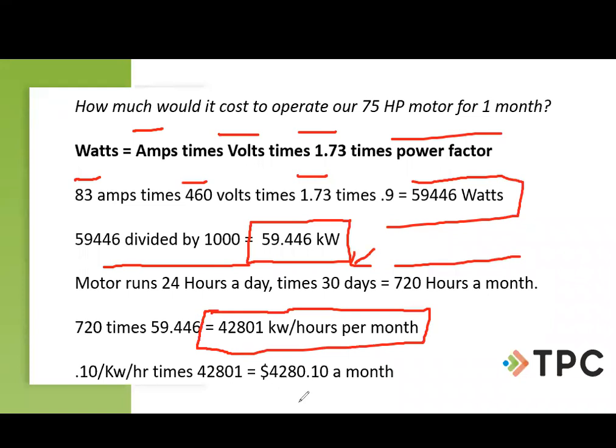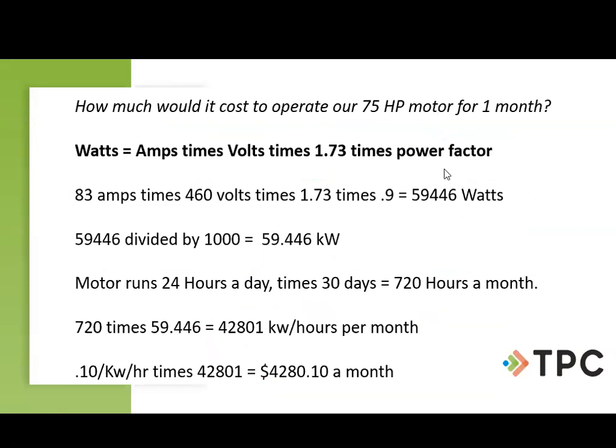And if the utility is kind to us and they're only charging us 10 cents per kilowatt hour, it's going to cost us over $4,000 a month to run that 75 horsepower motor. So that's a little calculation using three phase. So the advantages of three phase. And then after this, we are going to open it up to questions, just so you know.